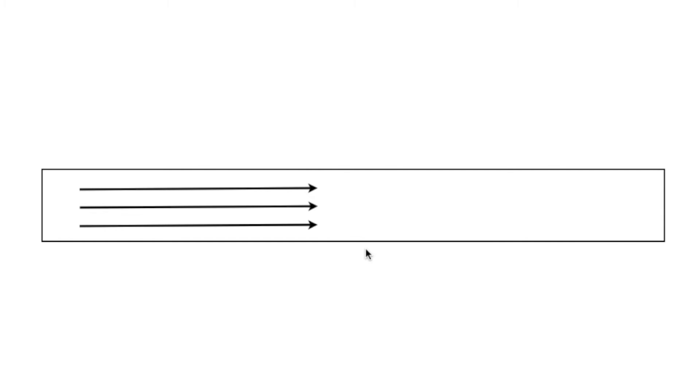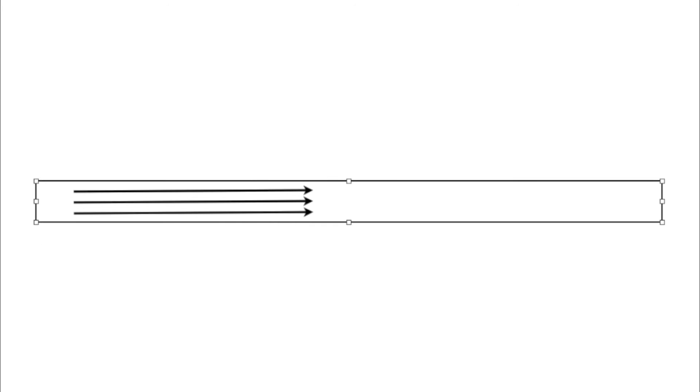Now remember this line, I'm showing a straight line here. This line could be curved, it could be going up, it does all sorts of different things. So let's reduce the size of this line and we'll see what happens. Okay, here you can see I've actually reduced this line. I still got the three lines in there, so I'm trying to move the same amount of gaseous refrigerant through here. But it's going to go much faster, the velocity is going to be higher. So it's going to drag this oil that's laying along the bottom with it. And that's the idea behind these things.